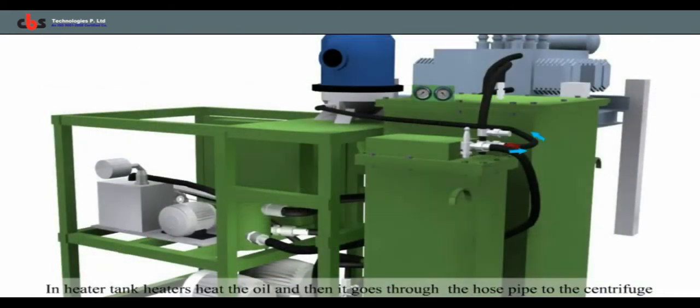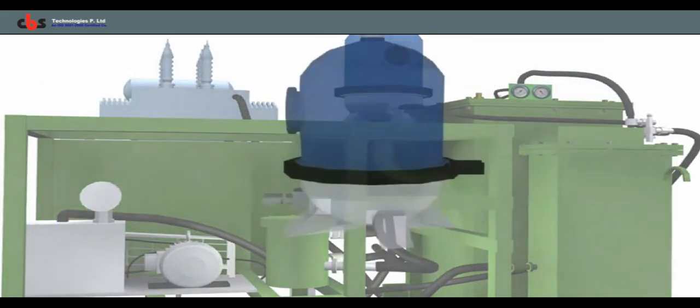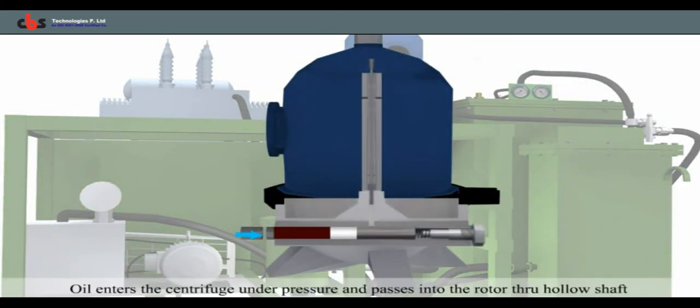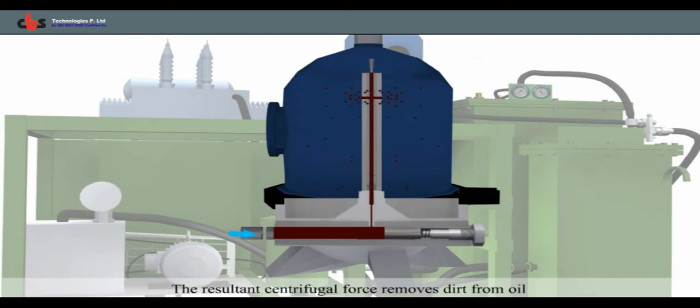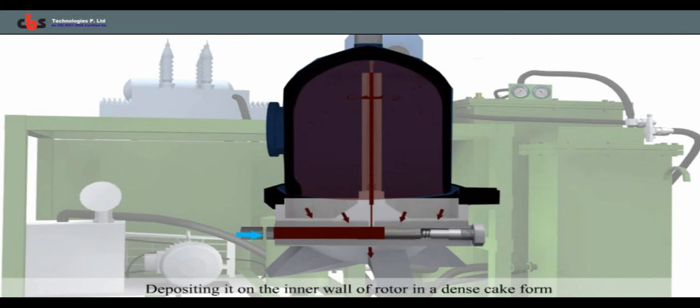This is done by maintaining the pressure of 5 kg with the help of gate valve. In centrifuge, oil enters under high pressure and passes into the rotor through hollow shaft, where solid particles like carbon and soot are removed with the help of centrifugal force.